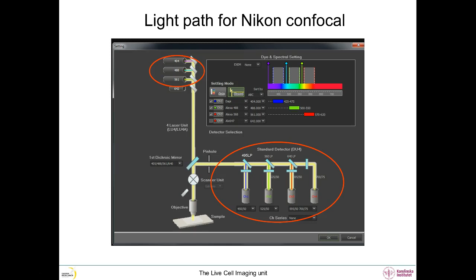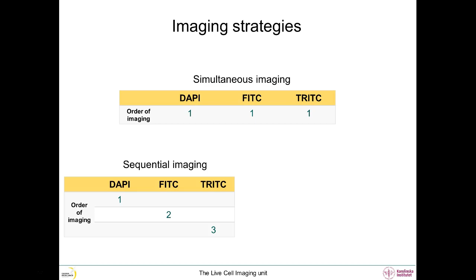This imaging strategy has the advantage of being fast, but any bleed-through issues will become a real problem because all the fluorophores are very well excited. In our example, we have seen that we have quite a few bleed-through issues. This means that we should not image the 3 fluorophores simultaneously. We need to image them sequentially instead. We will first excite DAPI with the 405 laser and collect its emission in the first detector. Then we excite and image FITC by turning on the 488 laser and the second detector. And finally we image TRITC with the third laser and detector. Sequential imaging helps avoid bleed-through, but the acquisition of the 3 images takes 3 times longer.